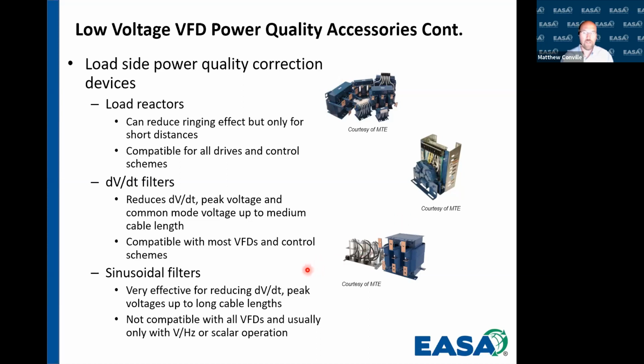And the last thing is sinusoidal filters. Sinusoidal filters are very, very effective for reducing DVDT and peak voltages for very long cable lengths. The problem with them is they're not compatible to be used with all variable frequency drives, and typically we only see them being used in volts per hertz or scalar operation. So if we're going to look at using any type of filtering, the major takeaway here is we want to work with the drive manufacturer to make sure that we're using the right one, and also that we're specifying the right one to reduce the DVDT and the peak voltage to a value that will be helpful for our windings.